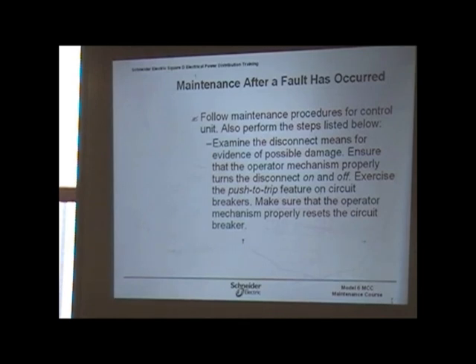A lot of people think that just because there's a pit or nick on busing, or on a current carrying conductor, it's okay to use - you can file it down and say it's good. But in reality, current doesn't flow through the middle of a conductor, it flows on the skin of it, and components are rated for a certain value because of the surface area.